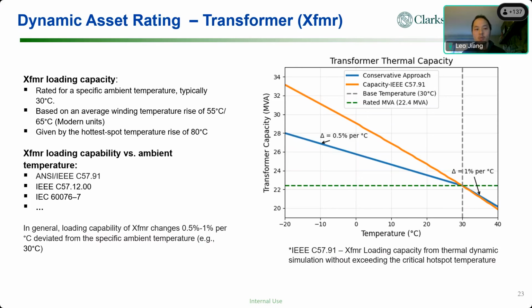Then it depends on what type of transformers, which year they were manufactured. They are based on a certain average winding temperature rise. Some units are 55 C or some units are 65 C. The modern units are primarily 65 C. That's for the insulation levels you have. And then really the limiting factor for the thermal loading of the asset, for example a transformer, is indeed the hottest spot temperature rise. Usually the modern units are 80 C. That's usually what your transformers are specified for.